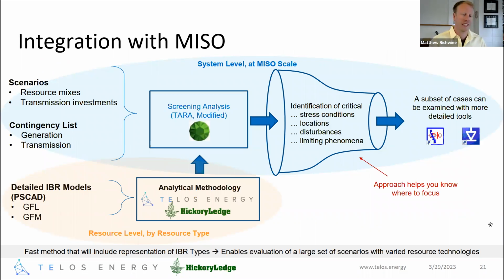So how do we use this? One thing we note is that those PV curves can be generated relatively quickly, and you can cover a lot of contingencies and a lot of future scenarios. Where we see this being used, particularly in integration into existing processes, is shown in blue on the top half: you have your typical steady-state contingency analysis where you've defined your scenarios with resource mixes and assumptions of resource mixes, transmission investments, and your contingency list—both generation and transmission—run through a steady-state analysis tool like PowerGEM's TARA, for instance.